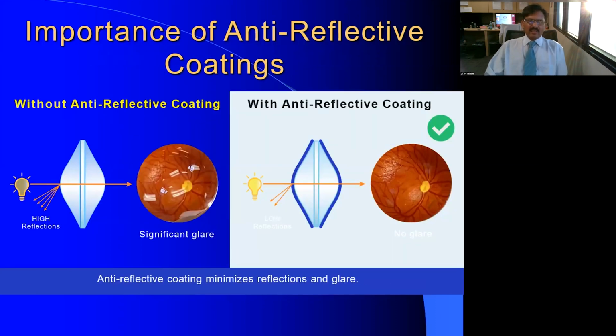So the second thing that I mentioned is the annoyance of the reflective images, because you're going through two surfaces of the lens and the cornea, as well as if somebody has an intraocular lens. So one way is to tilt the lens to avoid the glare. And the second way that is done by the manufacturers is the anti-reflective coating on either side. So it neutralizes the illumination coming back.